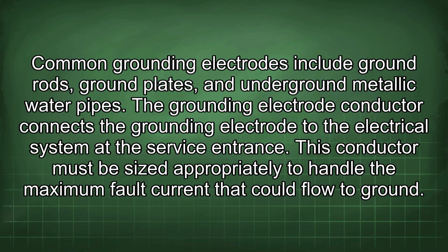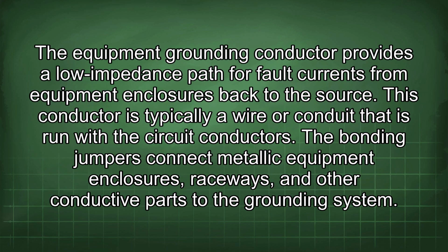The grounding electrode conductor connects the grounding electrode to the electrical system at the service entrance. This conductor must be sized appropriately to handle the maximum fault current that could flow to ground. The equipment grounding conductor provides a low impedance path for fault currents from equipment enclosures back to the source. This conductor is typically a wire or conduit that is run with the circuit conductors.